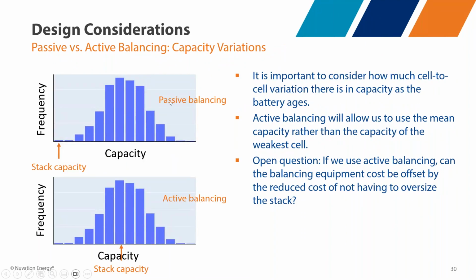This speaks to the capacity of the cells inside a system, and you'll get some normal distribution inside of that. In a passive balancing system, the stack capacity is limited by your cell with the lowest state of health energy, the lowest usable capacity. Whereas in active balancing, you can prop up those low cells while discharging, so you're limited more by the average usable capacity of cells in a particular stack.